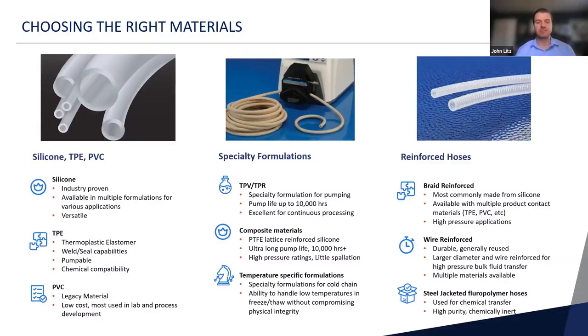Moving on to some specialty formulations, there are formulations on the market that are different than the silicones, TPEs, et cetera. And those you might see listed as a TPV, which is a thermoplastic vulcanizate, or a TPR, thermoplastic rubber. These are generally used for pump applications. And one of the reasons why they're excellent for pump applications is because in certain cases, they have pump lives up to 10,000 hours or greater. These products also tend to have fairly good chemical compatibility ratings. And when it comes to pump life, it's going to be far superior to your general silicones that you might use for general transfer.